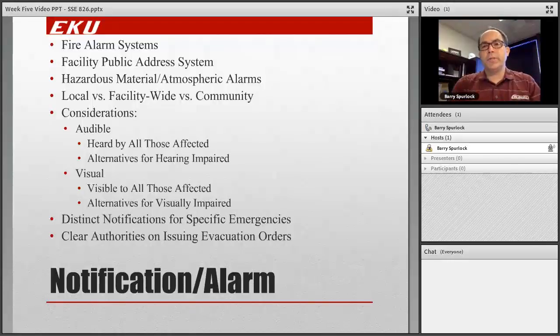Obviously, you'd have to look at your material and what a leak would mean and see, do we need a more sophisticated alarm? Do we need something that is more robust? So we'd have to look at the particular material. I've seen this a lot in wastewater treatment facilities or water treatment facilities that might be remote, where they're maybe storing chlorine gas or sulfur dioxide gas, and they have rooms where compressed gas is stored, and they want to monitor if there's a leak.